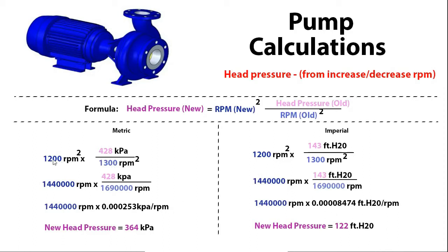But anyway, if we drop the numbers in and work our way through these very large numbers, we get all the way down to the new head pressure, which would be 364 kPa or 122 feet of water.